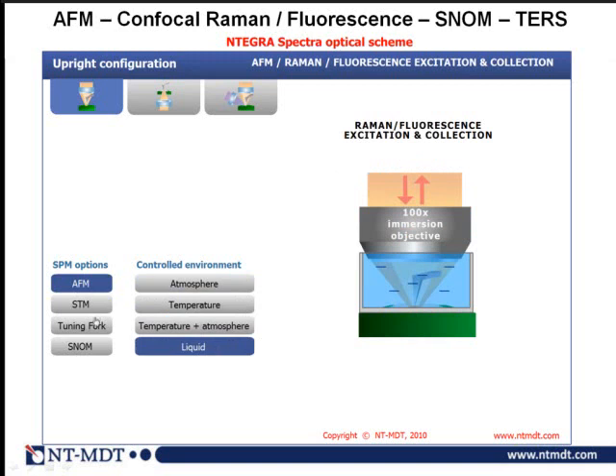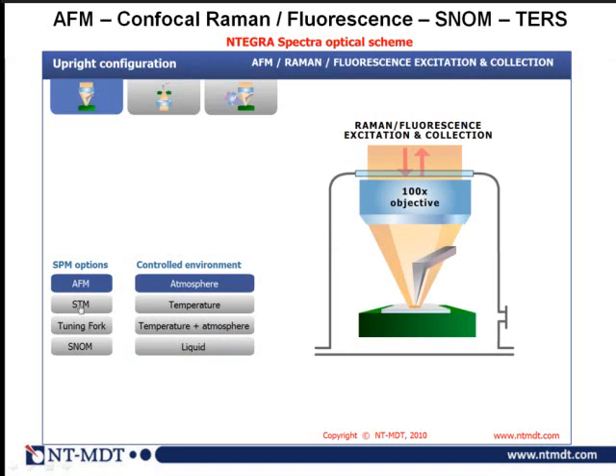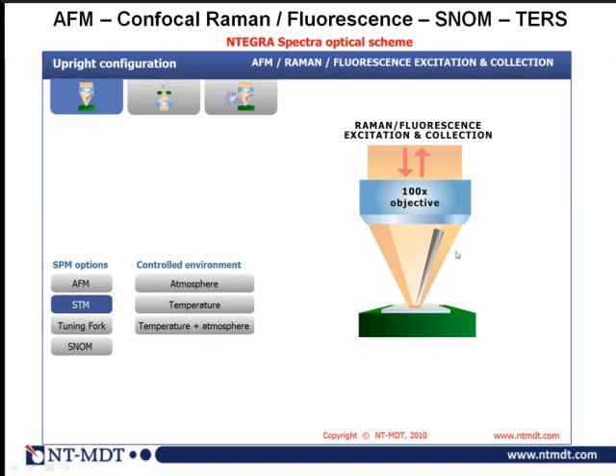An important capability is using different AFM probes. You can see the AFM cantilever under the high-resolution lens, but sometimes you want to use an STM tip instead. If the tip-enhanced Raman probe is an etched metal wire, it can be glued to a tuning fork; the tuning fork works as force feedback for the AFM, so effectively any sharp object can be used as a TERS probe.